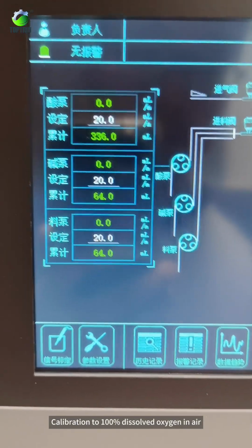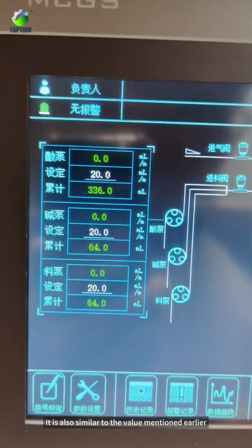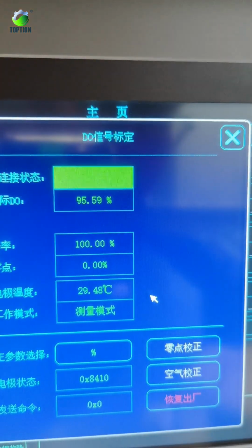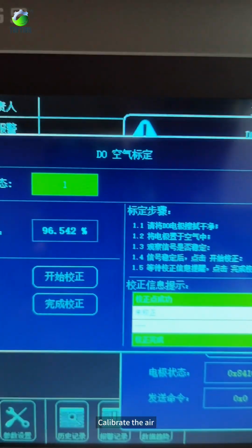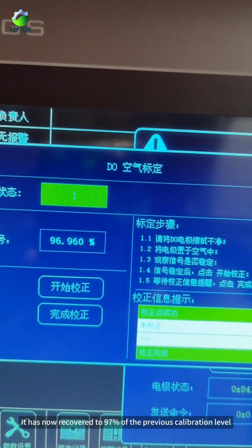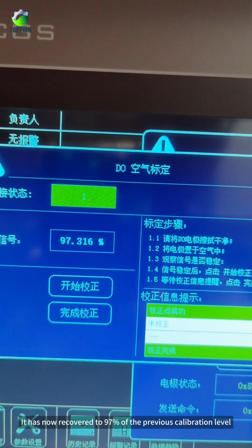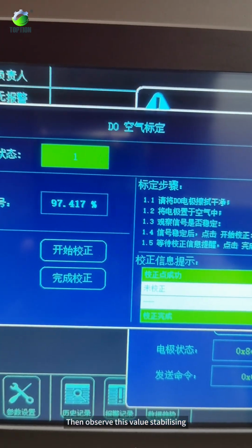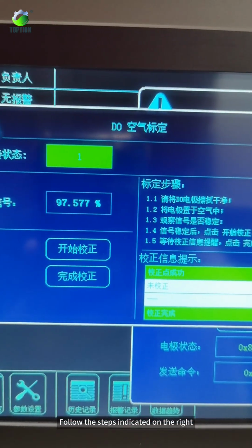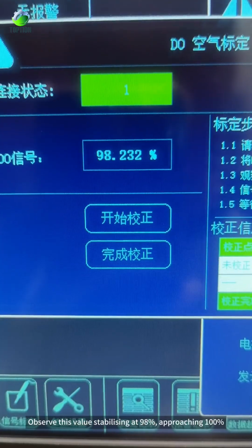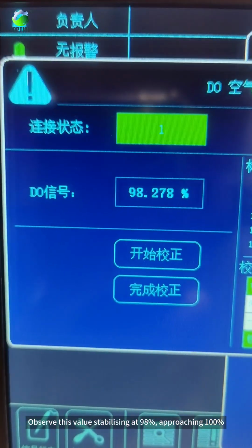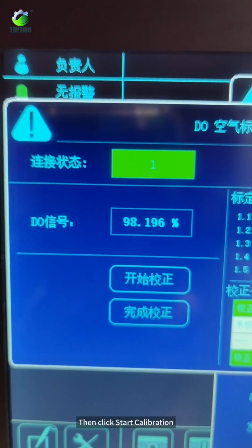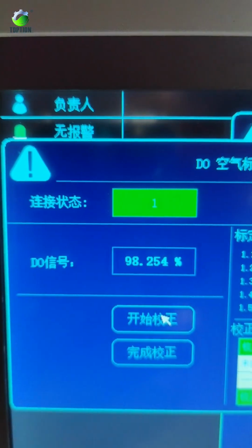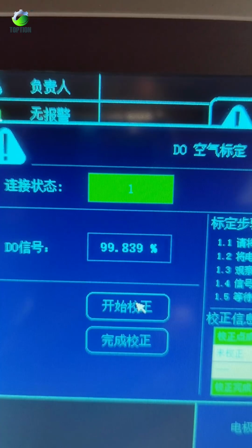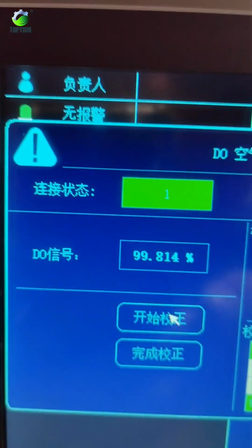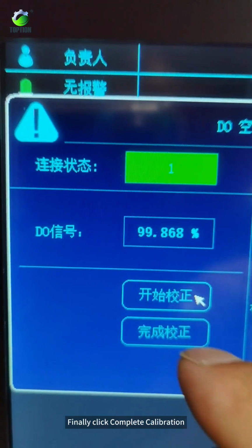Calibration to 100% dissolved oxygen in air. It is also similar to the value mentioned earlier. Calibrate the air. It has now recovered to 97% of the previous calibration level. Then observe this value stabilizing. Follow the steps indicated on the right. Observe this value stabilizing at 98%, approaching 100%. Then click Start Calibration. Finally, click Complete Calibration.